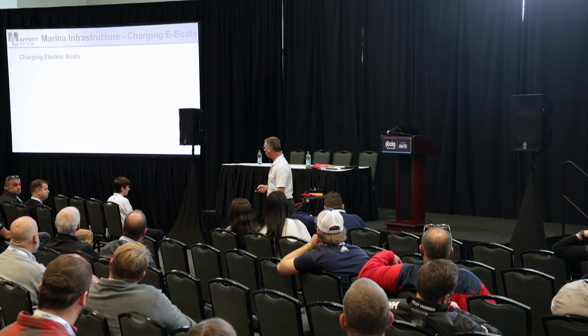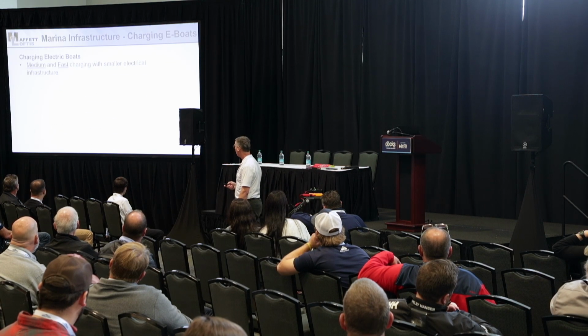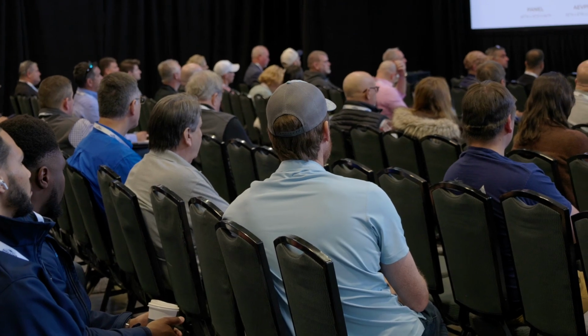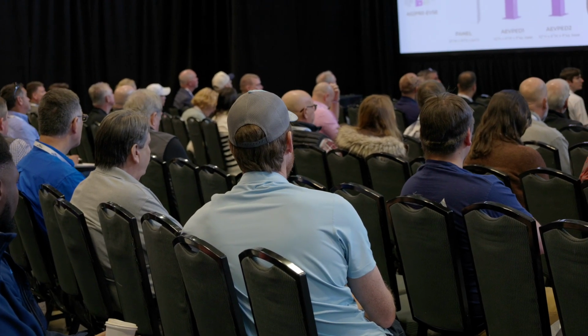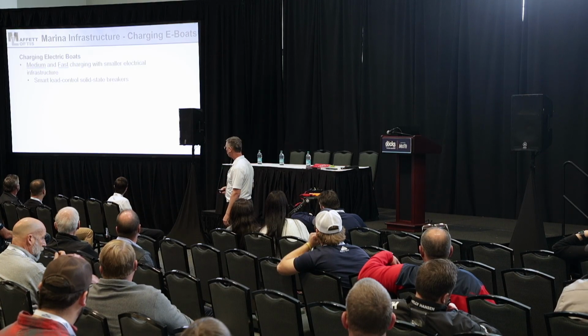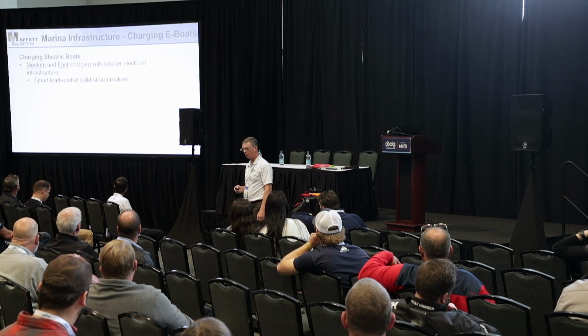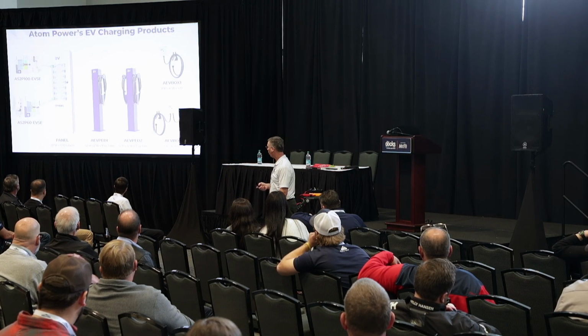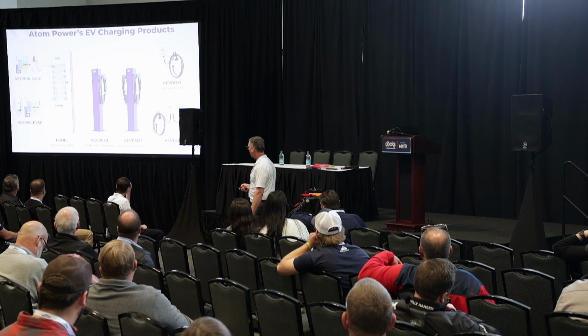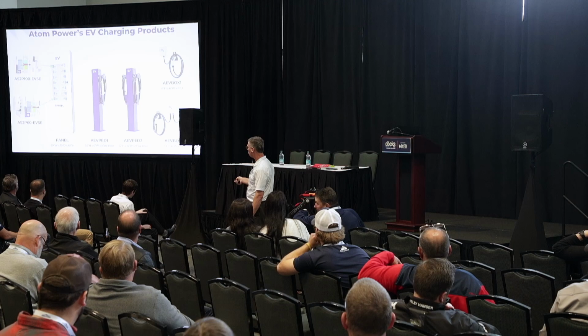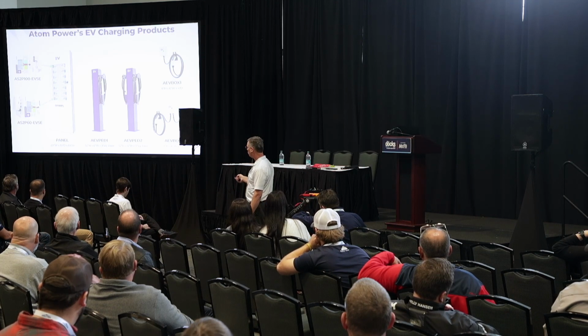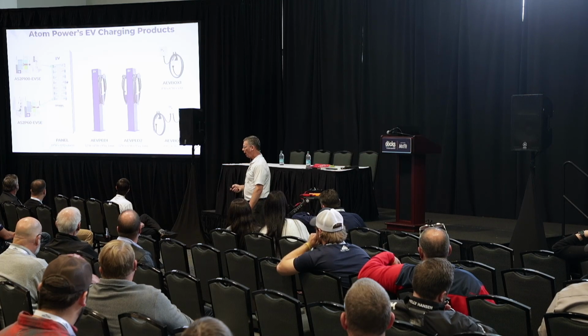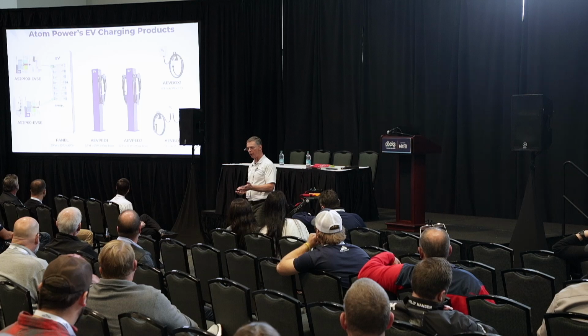I've got an example of what this could be, say charging electric boats. Of course you can do fast charge, or fast charge and medium charge, but these solid state load control systems — I've got a graphic here from Atom Power, this Atom Power. What we can do is have 400 amps coming into this switchgear, and this switchgear is not your typical switchgear, it's a motor control system. We can have 400 amps coming in, and that's what they rate this at — the incoming bus is 400 amps.